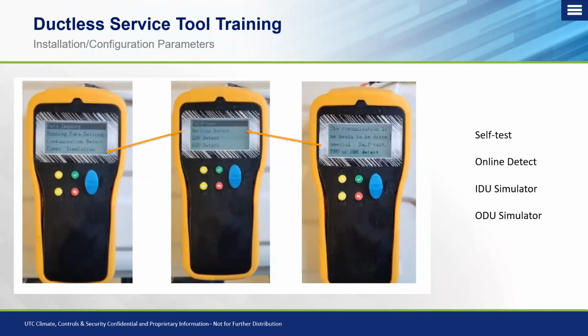So getting into here through your indoor unit, this is going to be your self-test menu, your online detect menu, your indoor unit simulator, and your outdoor unit simulator. This is going to be done through your L, N, and S connection that you will receive with the tool. So when you power this on through your L, N, and S connection, you want to go down to your communication simulation tab and hit your green arrow to get into it. And you'll see in here you have these different menus: self-test, online detect, indoor detect, outdoor detect. Depending on what you want to do is what menu or feature you're going to want to select on there.